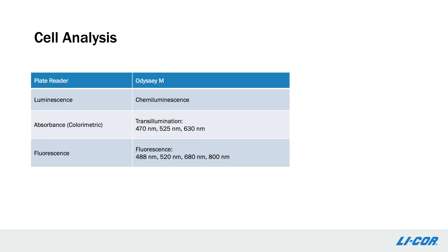Cell analysis assays are detected either by luminescence, absorbance, or fluorescence. As shown in this table, Odyssey-M has comparable channels for each of these detection modes. While the transillumination and fluorescence channels on Odyssey-M are static, they are well-suited to many commercial absorbance and fluorescence-based detection kits. In the next few slides, I'll show examples of cell viability assays in each detection mode on Odyssey-M.